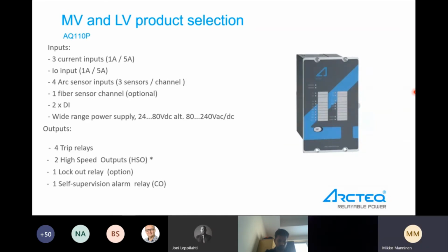Optionally, one fiber sensor, also this 110P device. And we can measure 3 current inputs, 1 amp or 5 amp, and that we can select from the dip switches. We can also measure earth fault current. I don't know that many cases where this earth fault current has been in use, so mainly this has been built with 3 current inputs only. But it is available.